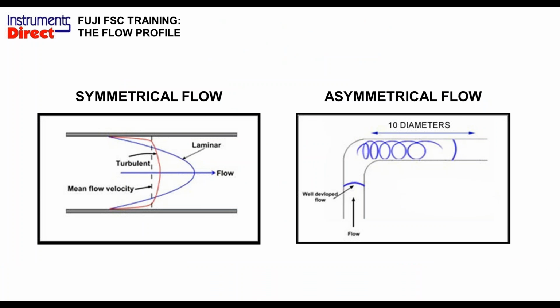Now, every ultrasonic flow meter, and for that matter most flow meters in the world, requires a certain amount of straight run of pipe. We call that a symmetrical flow profile. What it looks like inside the pipe with a symmetrical flow profile is that the flow is fastest at the center and slowest near the pipe wall. These different elliptical shapes are defined by Reynolds numbers. And what we're trying to do in this particular case is get an average across the whole cross-section of the pipe for optimum flow performance.